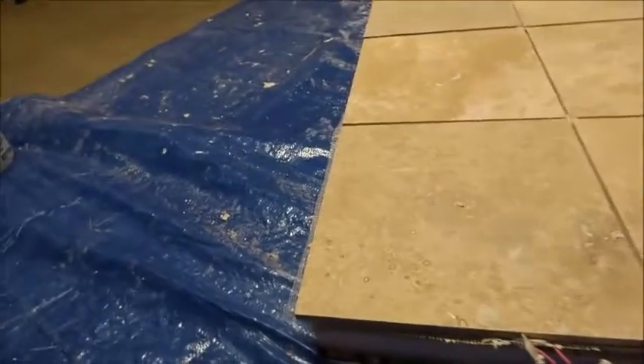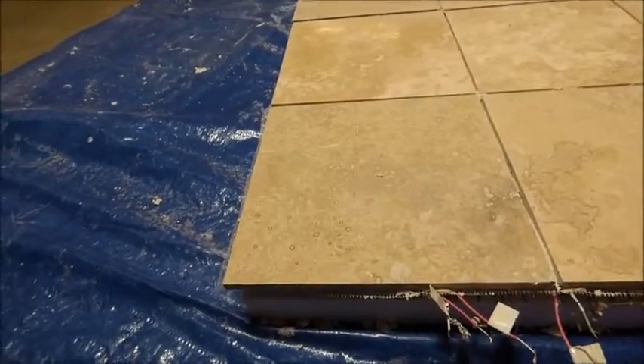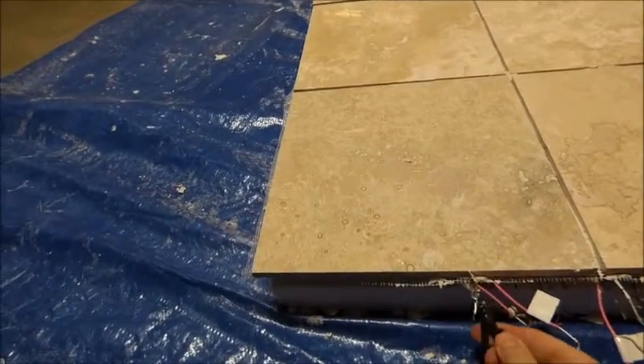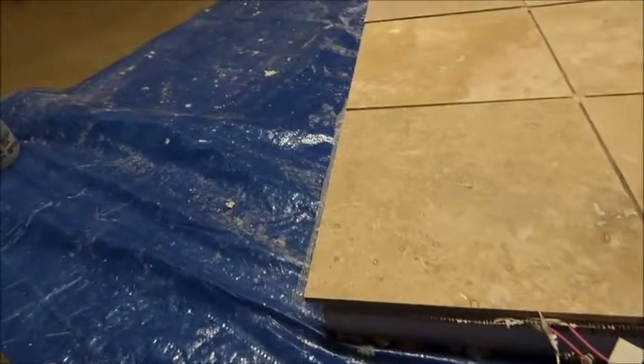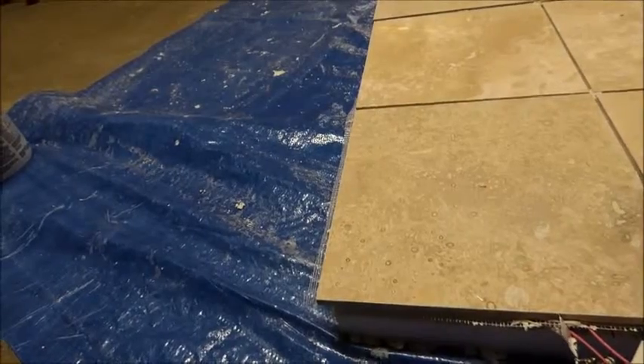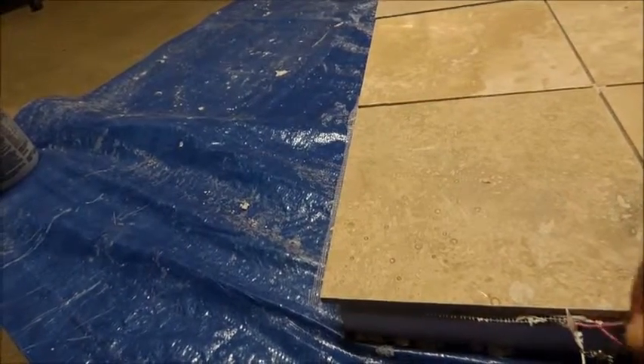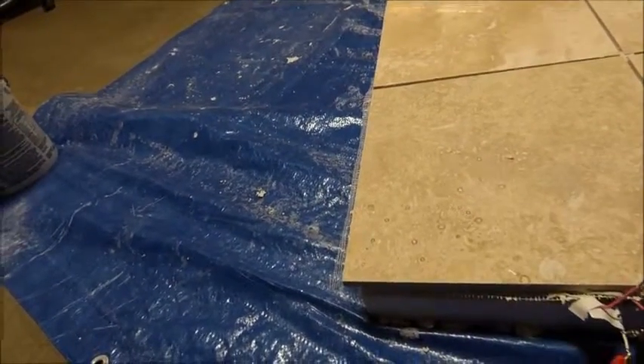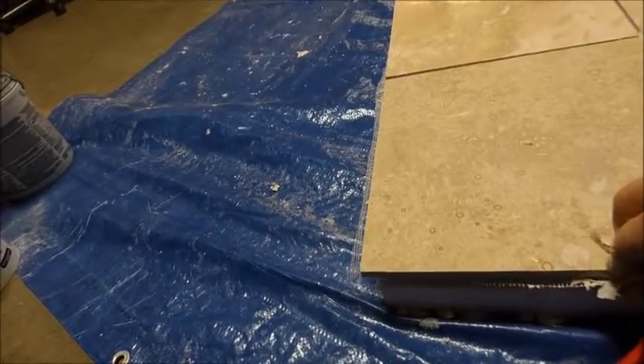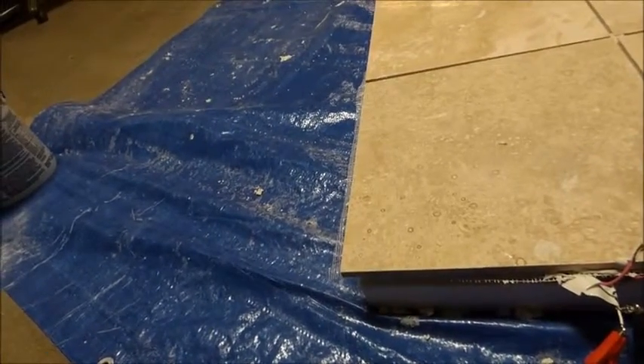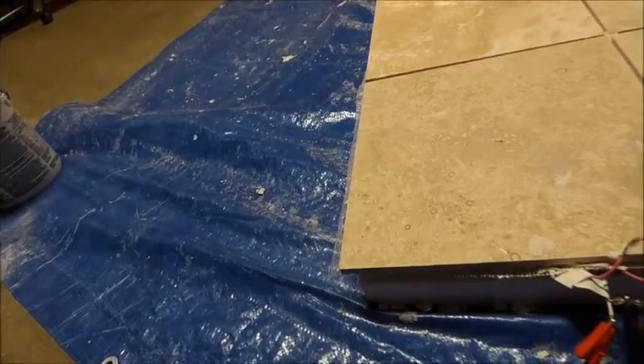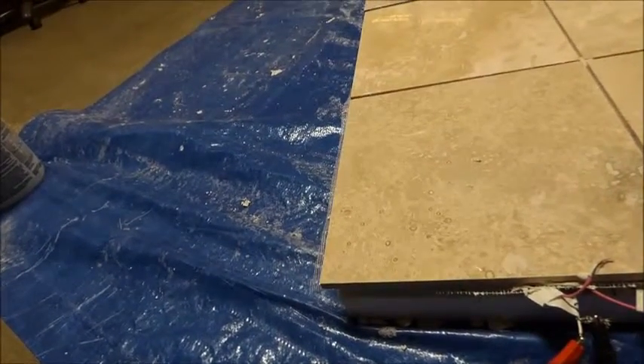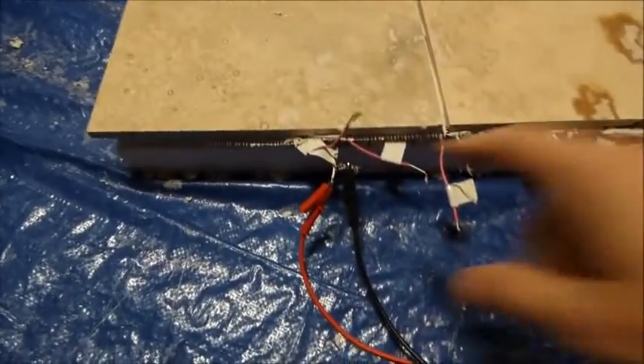So where is that ground fault? Well, black to the shield, red to the core, and trying to get this out of the way. So I've got a good inch of clearance between my high voltage electrodes and anything else.